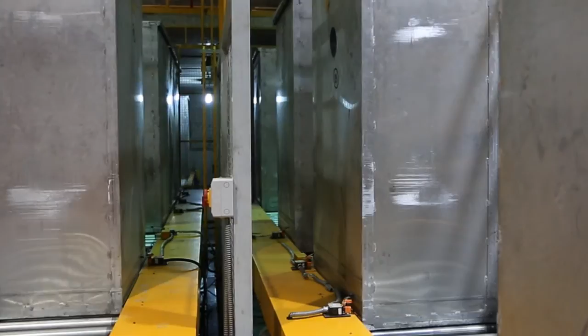Nipro India has started a state-of-its-kind gamma radiation facility, which is unique for the medical device industry. And this is the highest capacity of plant in India, with a capacity of 5 million curie, and it has a total strength of 1.5 million curie today. Gamma sterilization process. The products awaiting sterilization are stored in Nipro's huge godown. A dosimeter and a yellow sticker are attached to the cartons, which are then arranged in a tote box. These tote boxes are moved into the gamma sterilization plant, where the products are sterilized using gamma rays. The dosimeter and the yellow sticker change color after the process, indicating complete sterilization of the products within the box.